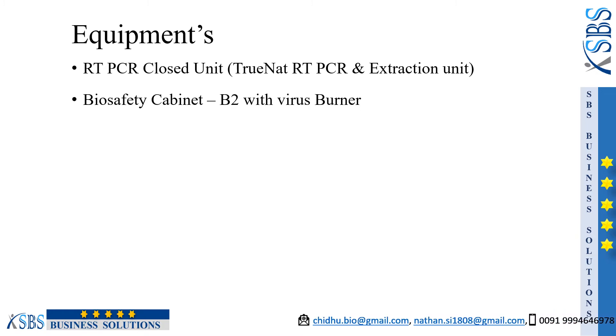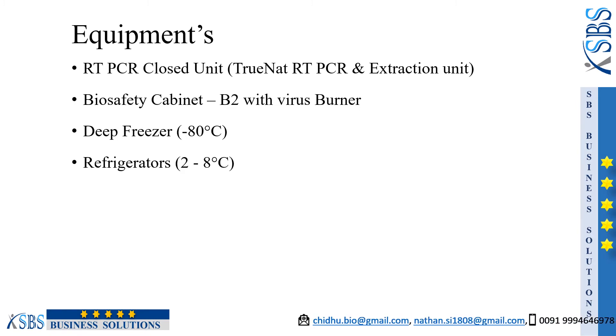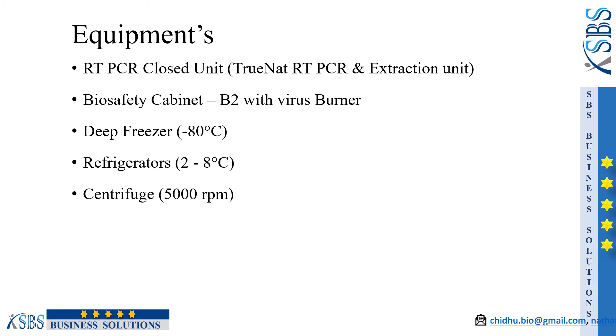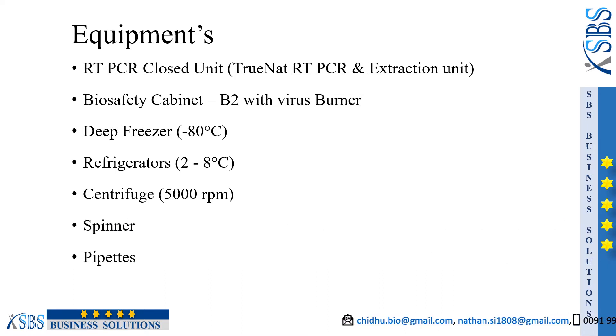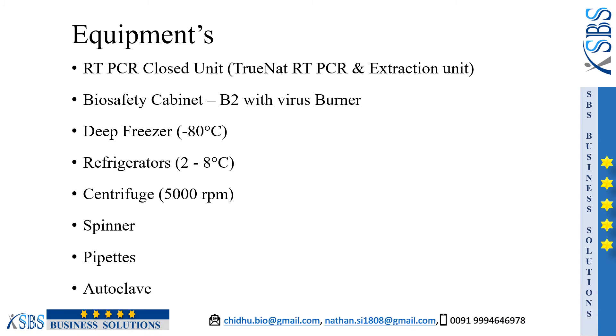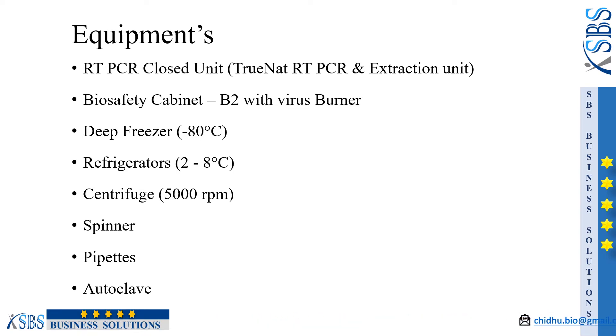Second one is a Biosafety Cabinet Level 2 with a virus burner. Then a deep freezer for RNA storage, a refrigerator at 2 to 8 degrees for kit and sample storage. Next, a centrifuge for blood samples to get processed for RT-PCR, a spinner, pipettes, and an autoclave for decontamination of Covid samples and the consumables used for testing the Covid samples.